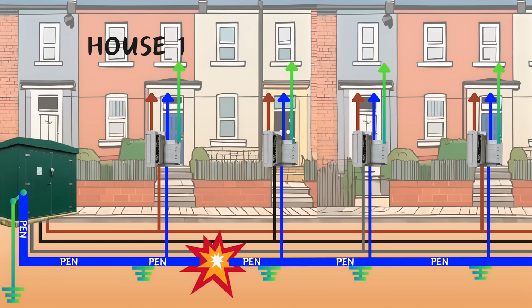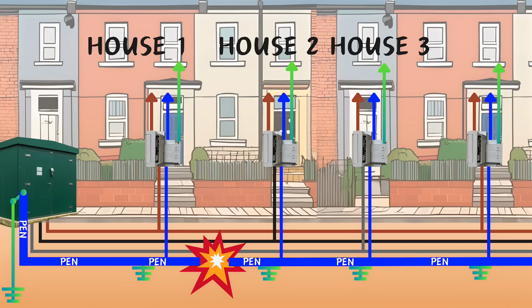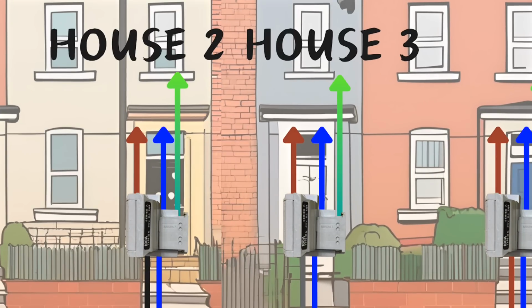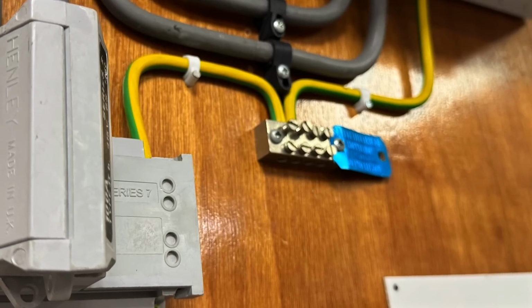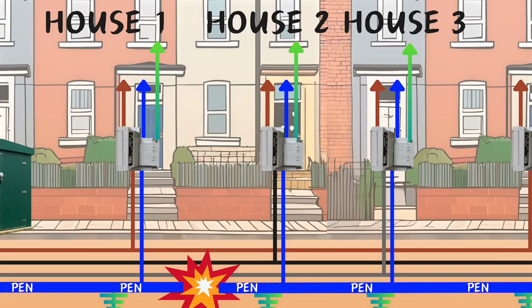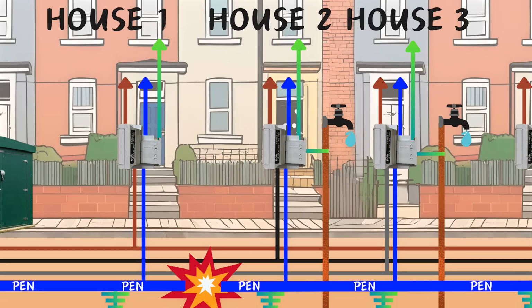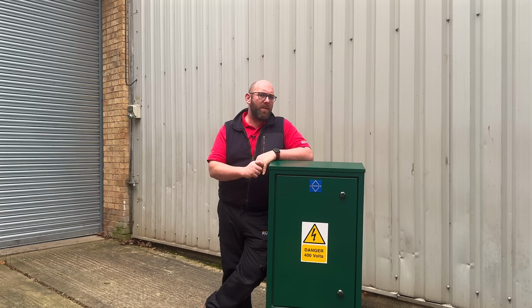In house 1, which is before the broken PEN, things are fine. Power is flowing and there is basic protection via an earth connection back to the earthing conductor. However, in houses 2 and 3, the neutral is broken, but everything is still working. How is this? Well, this is because our neutral and earth are combined, and they are combined here at the main earthing terminal, or MET. Also at the MET, we have connected a bonding conductor to the water, which has a referenced earth voltage of 0 volts. This means that even though the neutral in the road is broken, we still have a potential difference between line and neutral in the property.